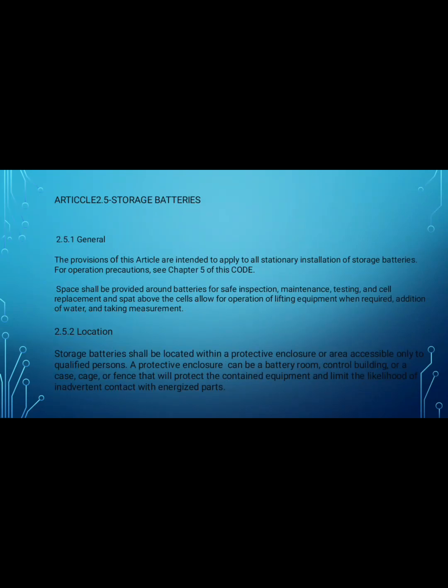Article 2.5 Storage batteries. 2.5.1 General. The provisions of this article are intended to apply to the stationary installation of storage batteries. For operation precaution, see Chapter 5 of this code. Space shall be provided around batteries for safe inspection, maintenance, testing, and cell replacement, and space above the cell to allow for operation of lifting equipment when required, addition of water and taking measurements.